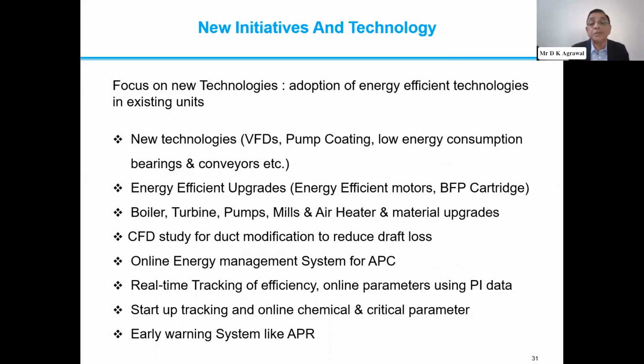And as has been mentioned in the presentation of Tata also, there are certain new technologies which we have to keep on adopting. Of course, some of the simple things are pump coatings and variable frequency drives. I have seen some plants of a very small size, maybe even less than 200 megawatt, that have gone for VFDs wherever needed, and they are getting the full benefit. Similarly, pump coating is not just for the CW pump; there is other equipment, ACW, your ash handling, where again they are benefiting from adopting those technologies. And energy efficient upgrades: there are some better profile impellers available for boiler feed pumps and so on.